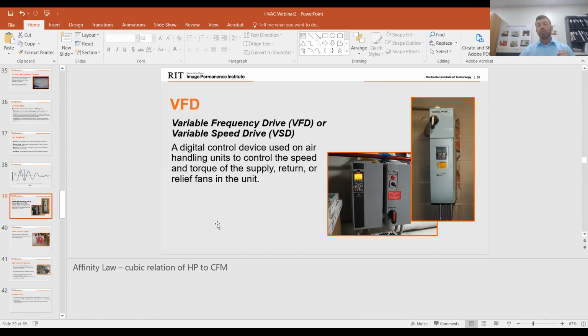Okay, well, that's great. We know you can do at least 4 hours. And you maybe started to lose condition. Can we look at a 3-hour shutdown? We're saving energy, and we know we can hold 3. So maybe we can do a 3-hour shutdown 2 or 3 times during the day. If we do 3 hours and then run for 6, and then 3 hours and then run, we can potentially save 9 hours worth of energy in the day if we're staggering that properly and we know the limits of our facility. So there are ways to work around it. It's just getting to know your facility and its ins and outs and limitations at the end of the day.